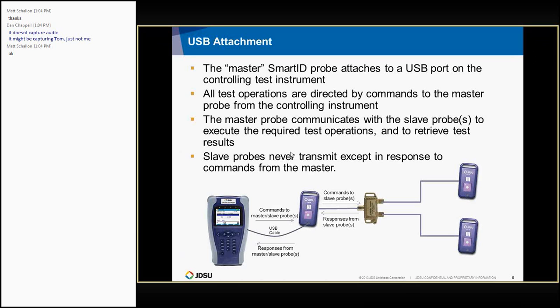So the master probe, you only attach one of these to a test instrument. If you were to connect another master probe on the same network to a different USB port, on another device, that other probe would also think it was a master. And when a probe thinks it's a master, it will not respond to any commands from other probes. It only initiates commands. So you only want one master probe on a network. So all test operations are directed by commands to the master from the controlling instrument. The master probe will pass on commands that are really aimed at the slave probe to execute whatever is required and to retrieve test results back and pass them on to the meter. And slave probes never transmit except in response to commands from the master.